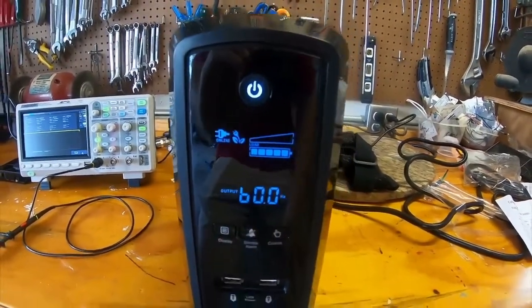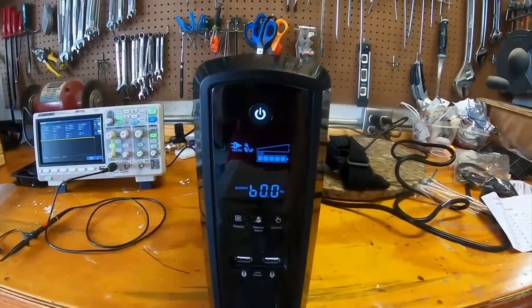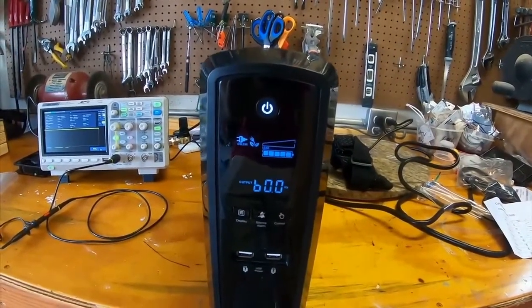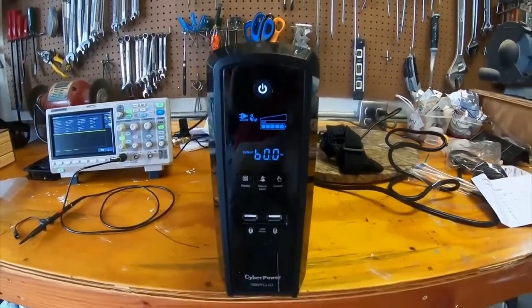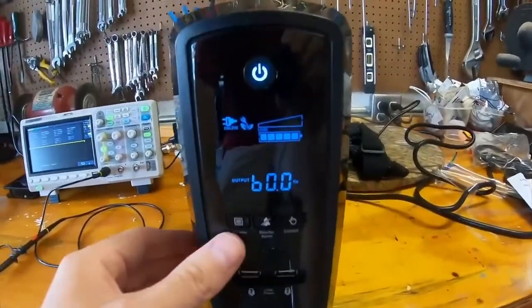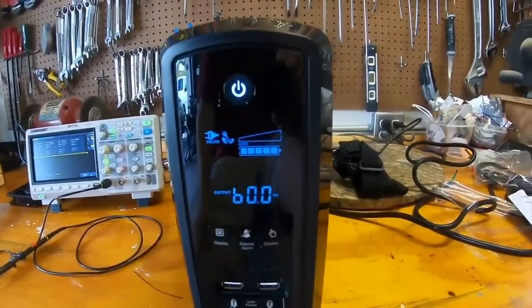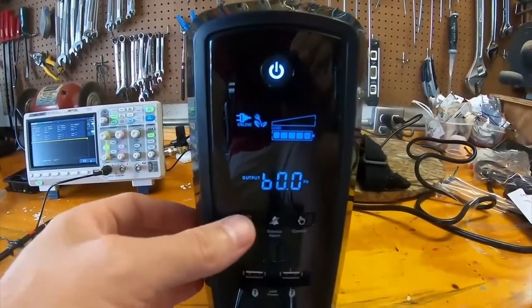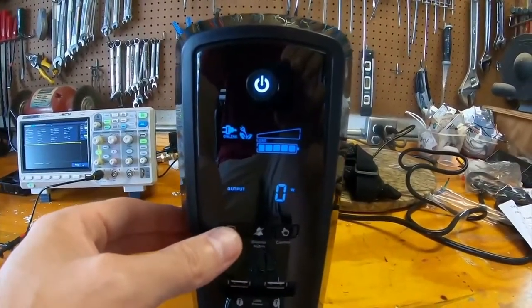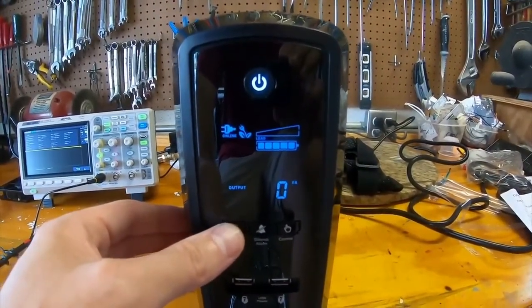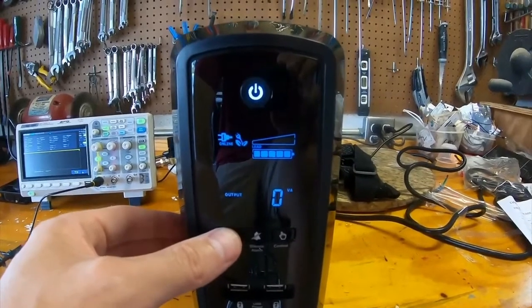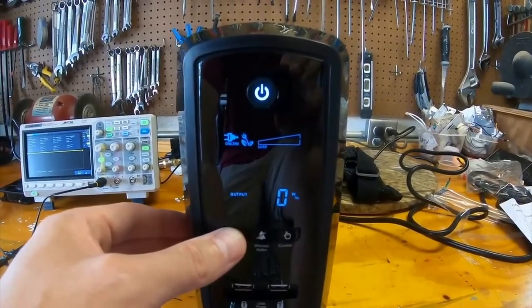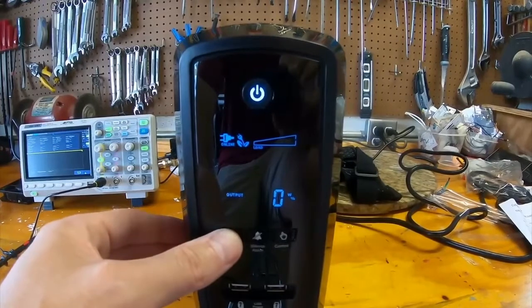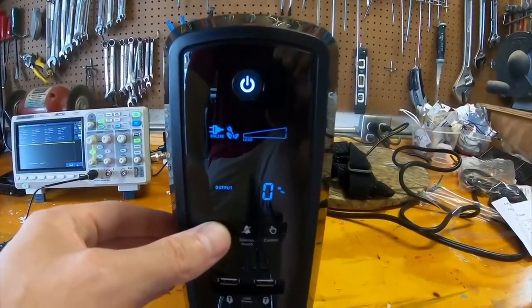This should be a line interactive power supply, and those types of power supplies do not condition the power that comes from the utility. So as long as the utility power is present and meets the standards this thing deems acceptable, it will just pass through that power. So if you have noisy utility power, this won't do anything to help you. They do make UPSs that will condition power, but they're far more expensive, way out of this price range.